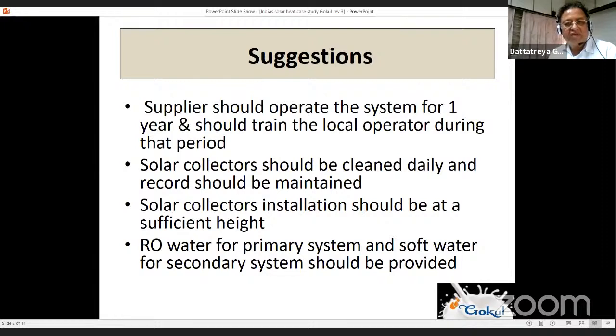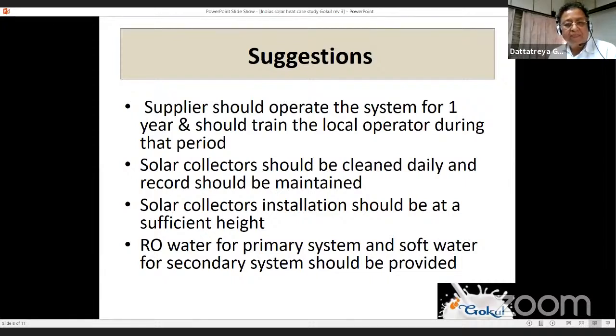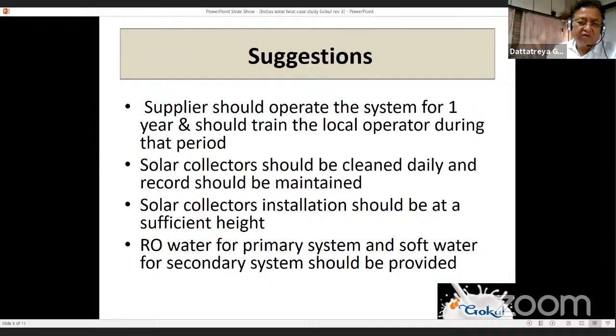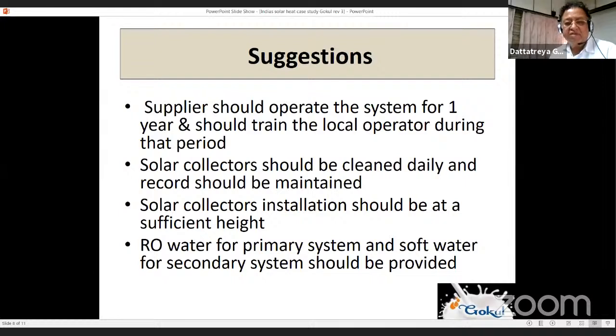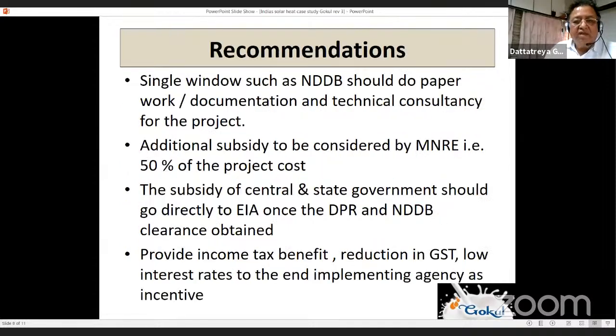A few suggestions: the supplier should operate the system for one year and train local operators during that period, as continuous operation depends on well-trained staff. Solar collectors need to be cleaned every day with records maintained daily — so you can look back and identify issues. Solar collector installation should be at sufficient height — even on a rooftop it needs to be elevated so cleaning can be done properly. RO water should be used for the primary system and soft water for the secondary system — raw water cannot be used directly.